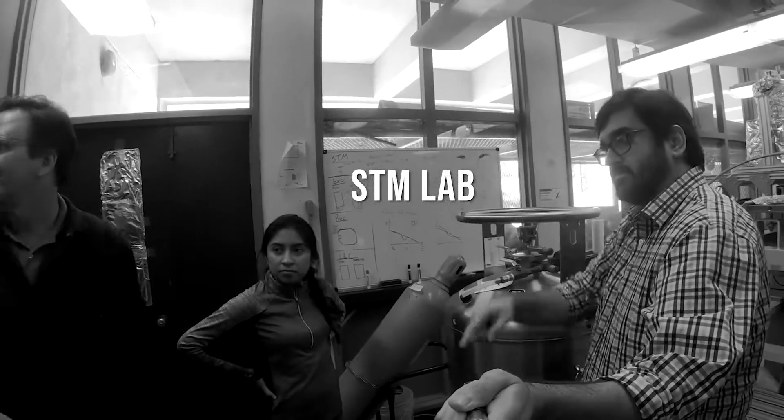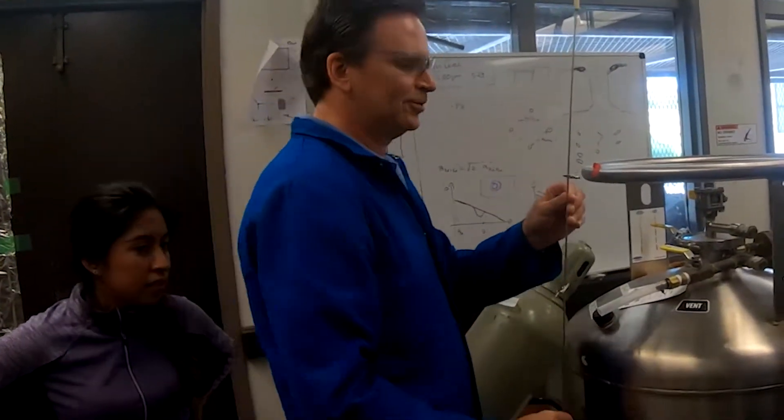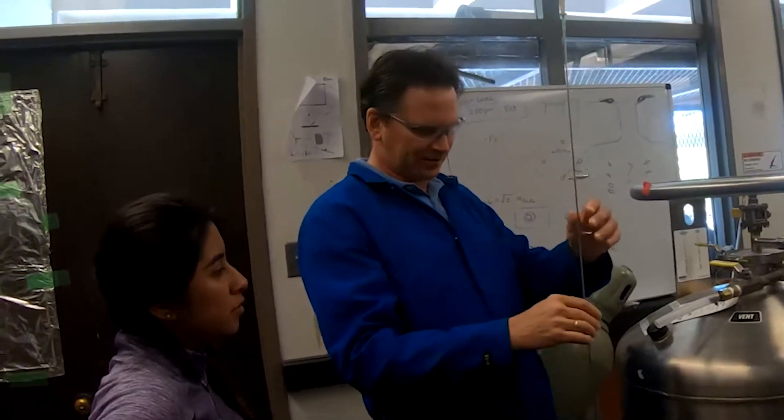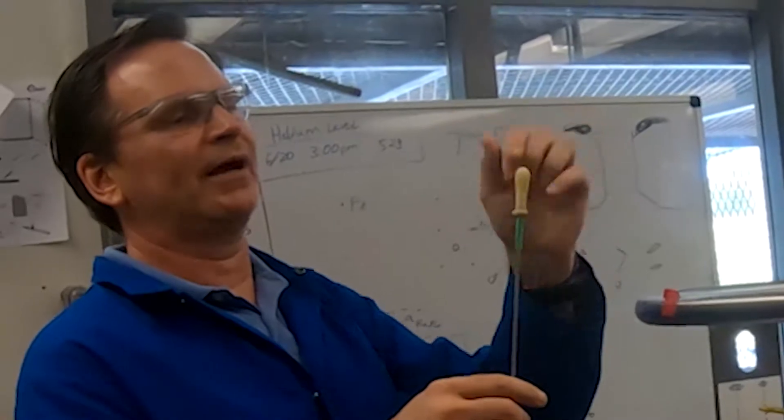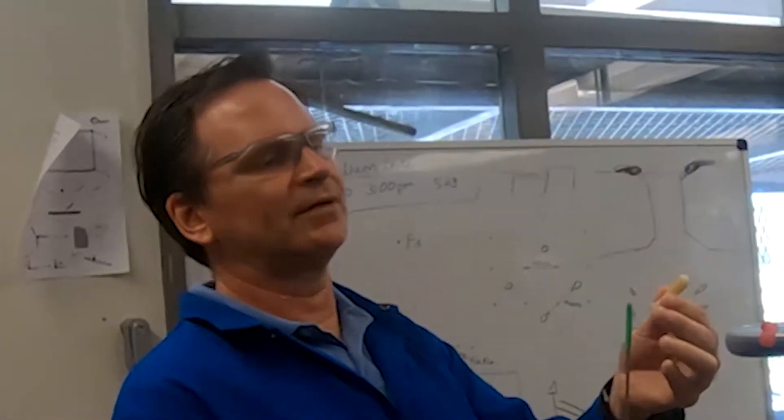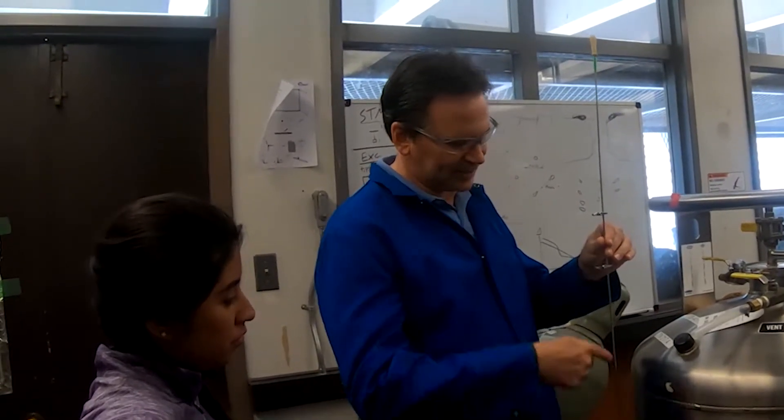There's a simple device called a dipstick, and it's just thin-wall stainless steel tube with a couple alligator clips for positioning along the tube. It's open on one end. On the top, we have a simple eyedropper bulb. That's just a simple open end tube. And then the temperature difference in here will give you thermal oscillations inside the tube.